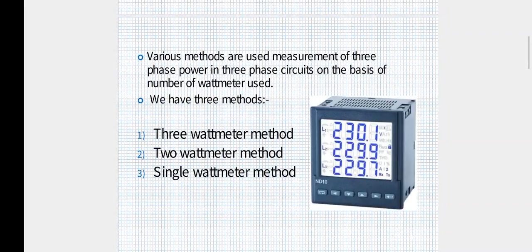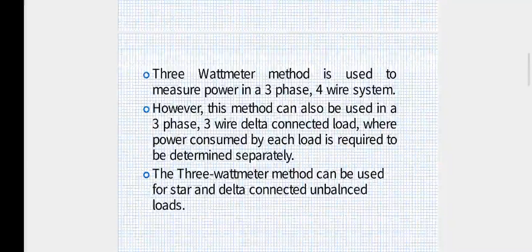The 3 wattmeter method is used to measure the power in a three-phase 4-wire system. R, Y, B and neutral is generally called the three-phase 4-wire system. However, this method can also be used in a three-phase 3-wire delta connected load, where the power consumed by each load is required to be determined separately. This 3 wattmeter method can be used for star and delta connected unbalanced loads also. So you can use it for star connection as well as delta connection loads.